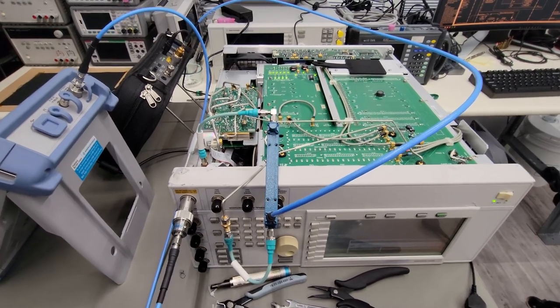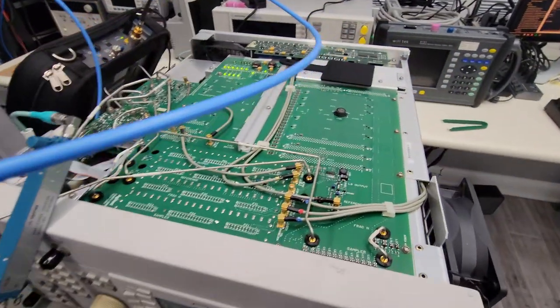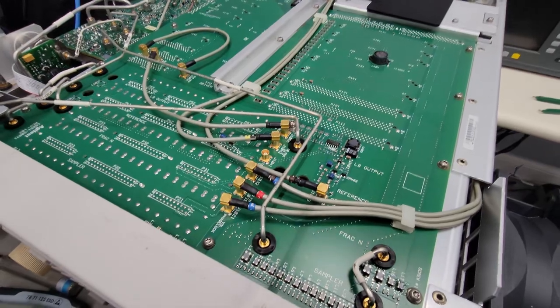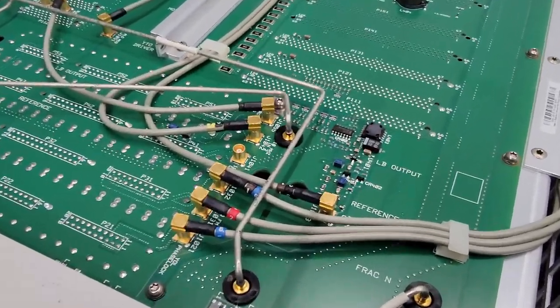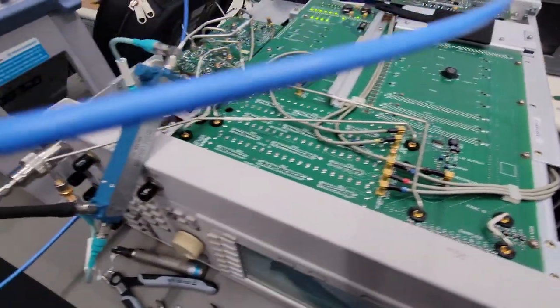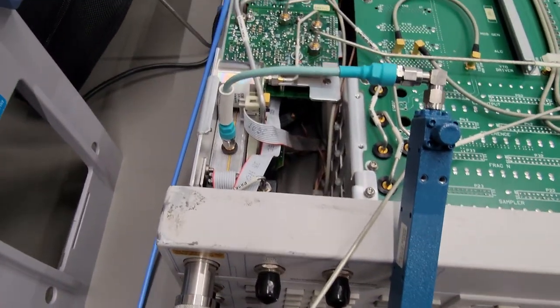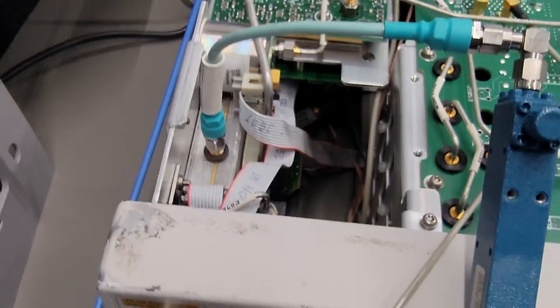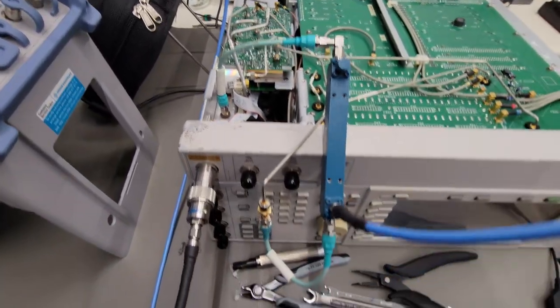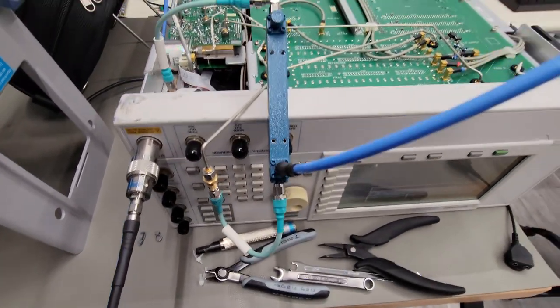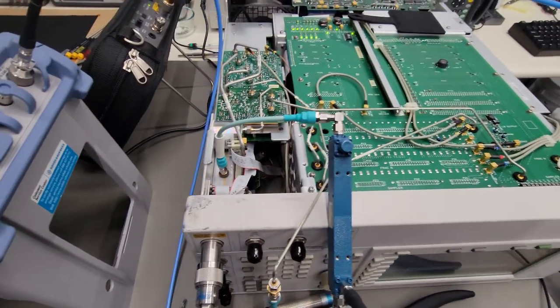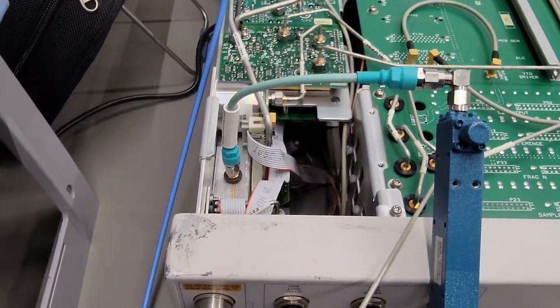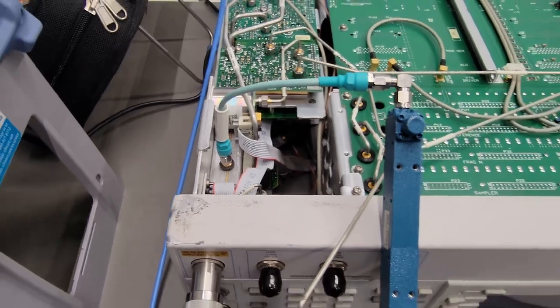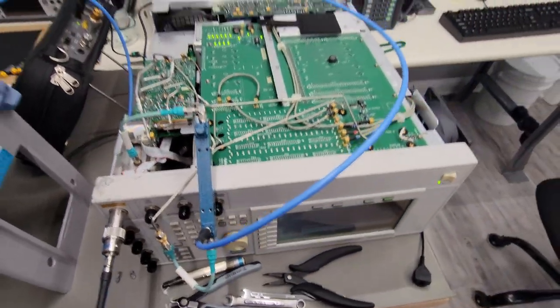Okay, so here's our next test. What I'm doing here is I'm looking at the amplitude of the low band signal coming out of the low band output here. And normally this cable would terminate into the low band coupler and detector, but I've bypassed that, so the output is going to the input of my directional coupler. Then the through path is going back into the low band coupler detector, but the coupled signal is coming out here.